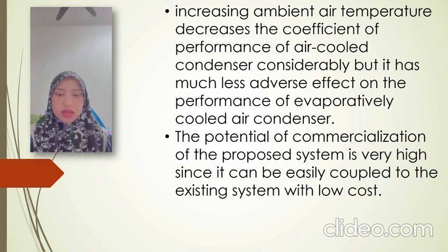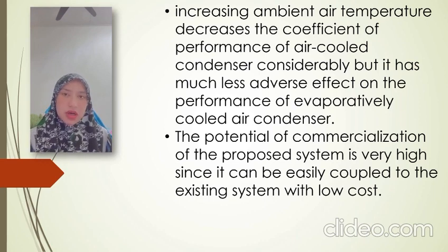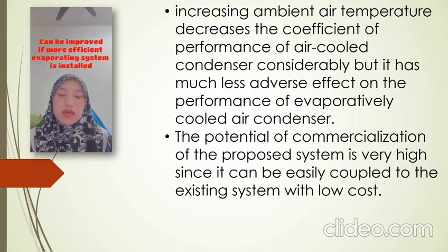The potential for commercialization of the proposed system is very high, since it can be easily coupled to the existing system at low cost. Application of the evaporatively cooled air condenser will reduce the peak load of the power network in hot weather areas because vapor compression air conditioners are usually responsible for the peak load. It was also found that the performance of the system can be improved if a more efficient evaporating system is installed.